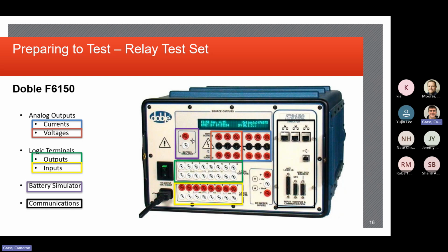stuff like that. The battery simulator, this is where you'll be supplying the DC to the test set from where the DC source is connected on the relay, to monitor and make sure that in the situation where there's a loss of DC to the relay, that type of command, the test set will be monitoring that as well. And then lastly, the communications port. These will be talked about a lot more Thursday when we're talking about end-to-end testing, but it's basically any of the communication parameters that will be dictated usually by a line relaying scheme where a relay is talking to another relay, possibly at another substation across the line. It could be within the substation as well, depending on the scenario. Basically stuff like that.